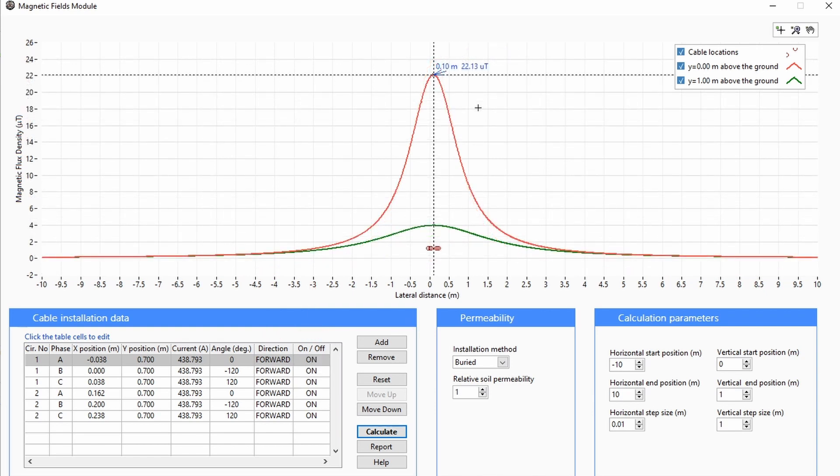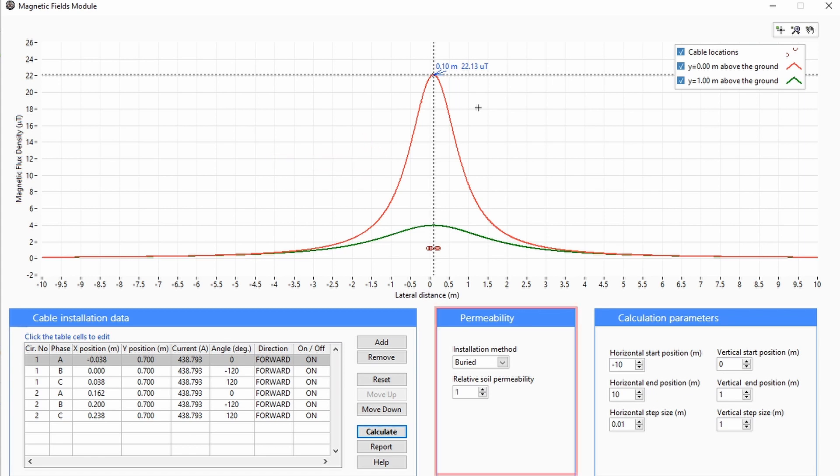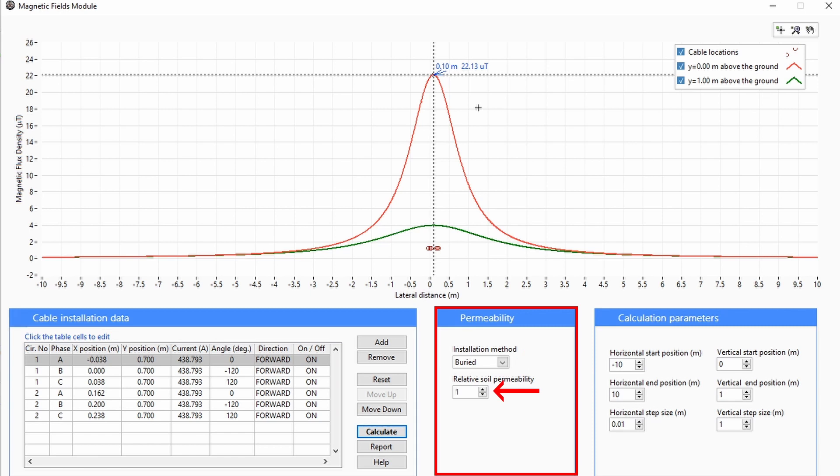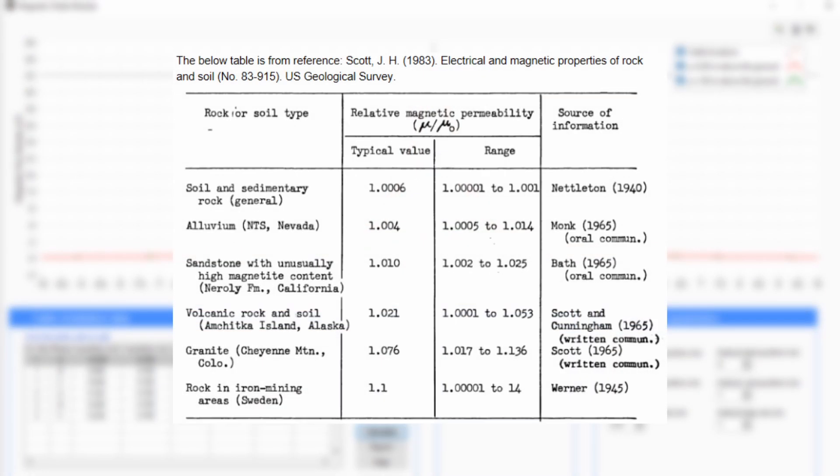Changing any of the parameters will affect the resultant magnetic field. The soil relative permeability can be changed for buried cables, but only has a small effect. The permeability of soil is only slightly higher than air. Here are some reference values for relative magnetic permeability of rock and soils.